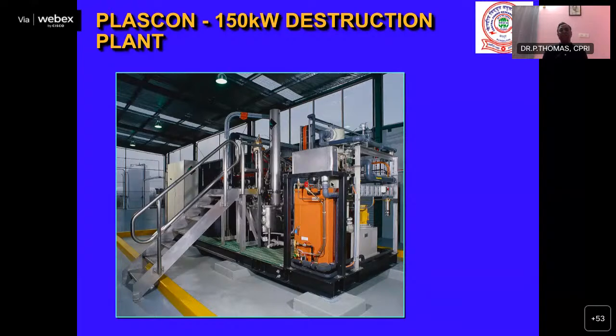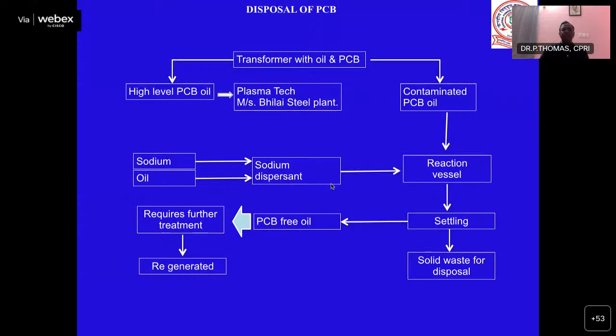This is all possible only when your transformer is very recently commissioned. If you look at the history of transformers, pure PCB oils are much older. Otherwise it is only a case of contamination. So there is a chance that a newly installed transformer can also be contaminated with PCBs. If that oil has contamination, it can be easily removed because these transformers are recently commissioned, so it will not be very high ppm. What we found is that most of the transformers are 500 ppm and above, but less than 10,000 ppm. As I said, transformers with high-level PCBs, pure PCB transformers, will all go to the Plasma plant.